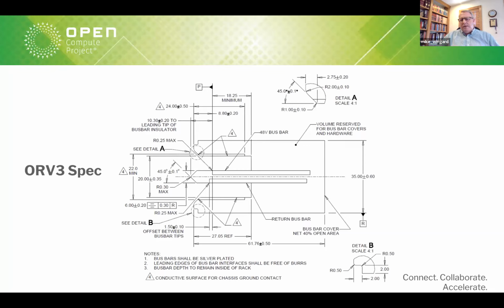Detail B shows another feature pointed out in the connectors presentation: the clearance allowance for the screw heads in the screw and washer float design for the connector. Due to tolerancing, there could potentially be an interference fit preventing a full mate between connector and bus bar. So in the bus bar design we've notched those entry points to allow full unrestricted float of the connector so the screw does not interfere with the cage.